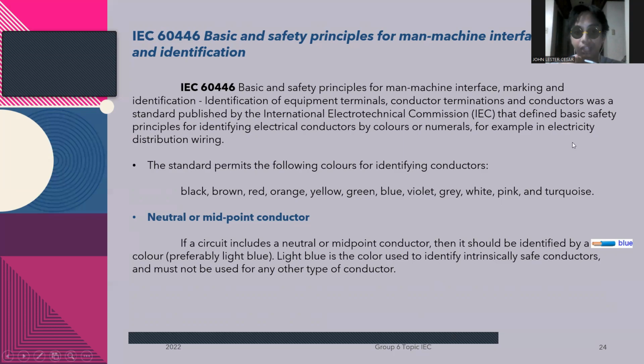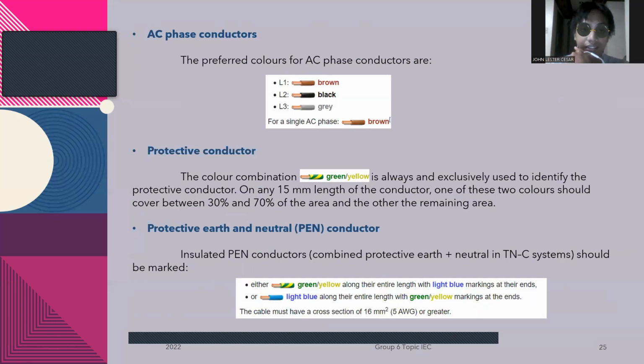Neutral or midpoint conductor. If a circuit includes a neutral or midpoint conductor, then it should be identified by a light blue color. Light blue is the color used to identify intrinsically safe conductors and must not be used for any other type of conductor. Next are the AC phase conductors. The preferred colors for AC phase conductors, this is for three-phase: for line 1, we have brown; line 2, we have black; line 3, we have grey. And for a single phase, we have brown.